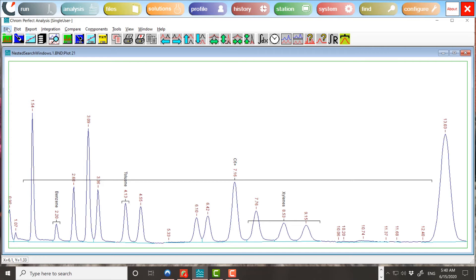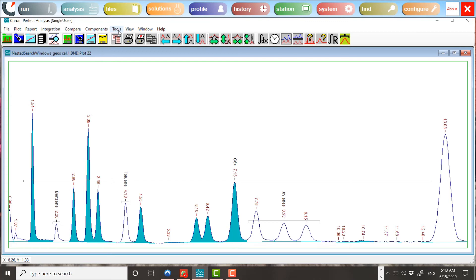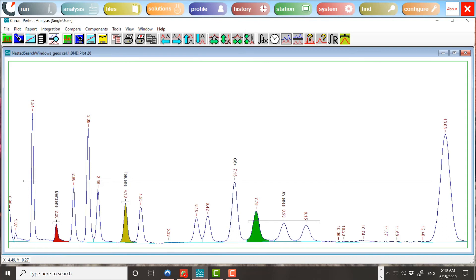The following illustration shows this calibration file applied to a chromatogram. We wish to report an amount for all peaks under the C6 Plus window, based on the sum of the peak areas, and using a response factor suitable for alkanes. We also wish to exclude several peaks from this multi-peak window: benzene, toluene, and the three xylenes. Furthermore, we wish to report amounts for these aromatic components using individual response factors. The three xylenes will be reported as a single component.